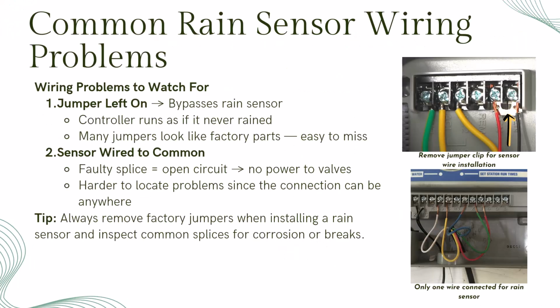Most rain sensor issues come down to wiring mistakes. One of the most common is leaving the factory jumper in place after the sensor is installed. That jumper completely bypasses the rain sensor, so the system runs even during rainfall. Another problem happens when the sensor is wired to the common wire instead of the sensor terminals. If that splice fails anywhere in the circuit, everything downstream loses power, and finding that bad splice can be a real challenge.